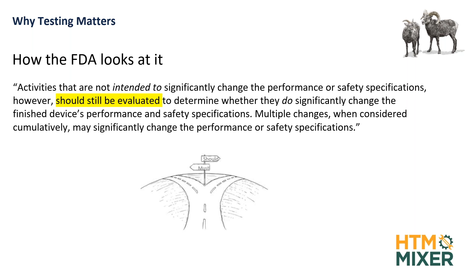You can't just duct tape together two cleared products from different manufacturers, a tube from Dunlee, Philips for the X-ray device. Duct taping those both together, even though both of them were cleared, they were never cleared together as a device. And so there's testing that has to be done by Dunlee, and they have to go through a lot of stuff. So this extends to everything, and we'll see that in some of the examples when we get there, that it doesn't always turn out the way people think it would by using a non-OEM part. And you'll learn a few questions you need to ask in that as well.